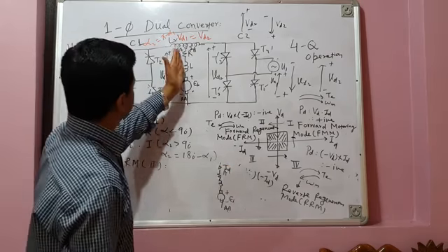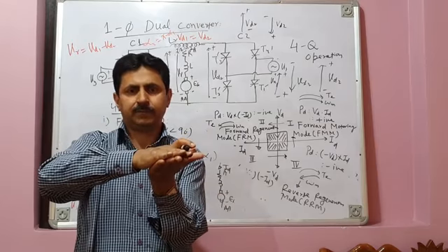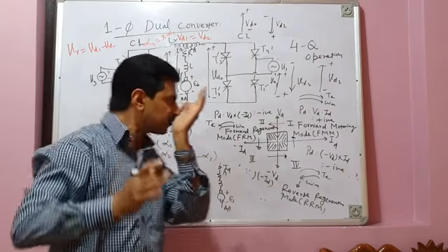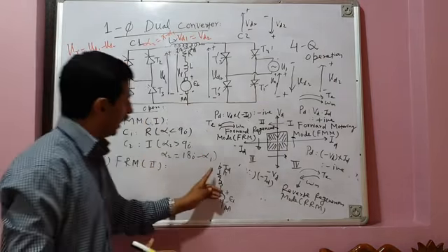Now when this current reverses its direction, that makes current negative, and your machine will operate as a generator, and it will generate the energy, feed that energy back to the source, and regenerative braking will take place. Torque will reverse its direction, and it will put an electrical brake on the machine. The machine will slow down and stop. That's what we want. Now, negative current means current should come out of armature terminal A.